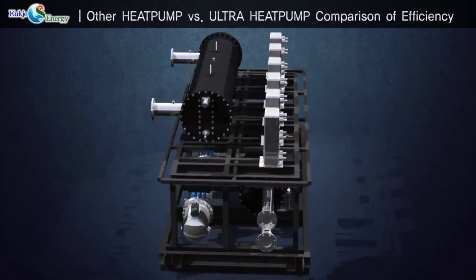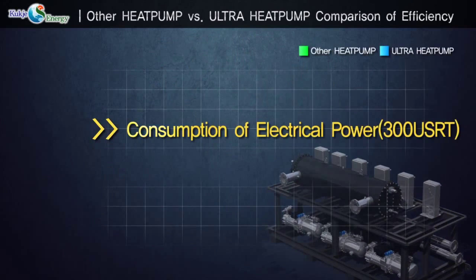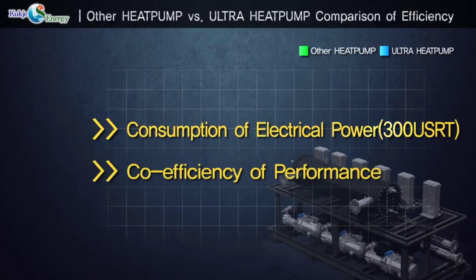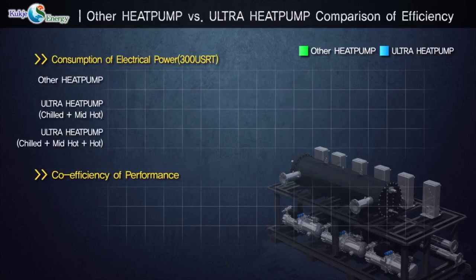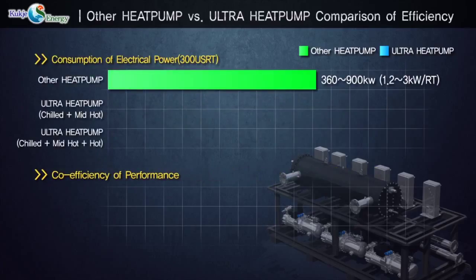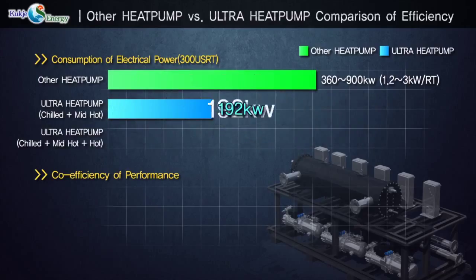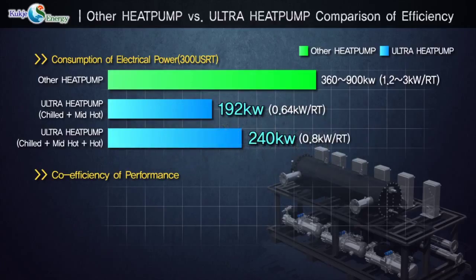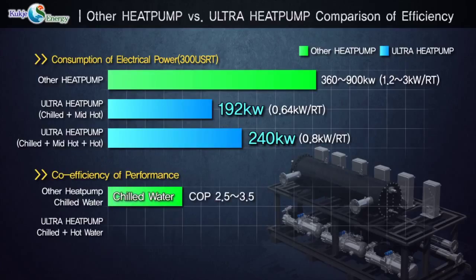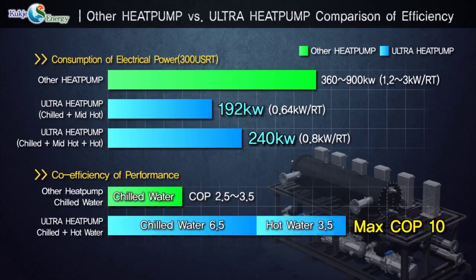The ultra heat pump offers enhanced performance compared to conventional heat pumps. One of the biggest differences is the power consumption and efficiency, or COP, coefficient of performance. In the case of a 300 RT class pump, the rated power consumption of a conventional heat pump is between 360 to 900 kilowatts. But the ultra heat pump only uses 192 kilowatts when producing hot and cold water simultaneously, and 240 kilowatts when producing hot and cold water separately. While the efficiency of conventional heat pumps is rated at COP 2.5 to 3.5, the ultra heat pump's sum of cooling and heating COP is over 10.